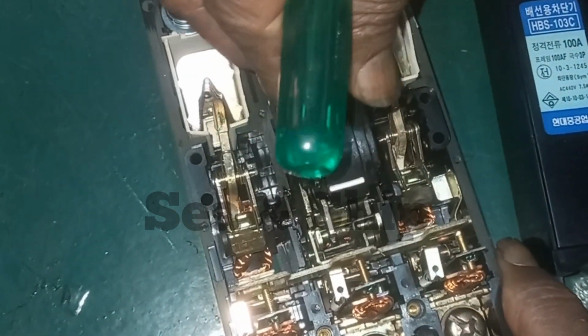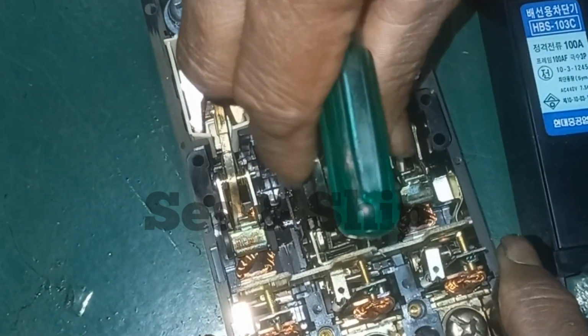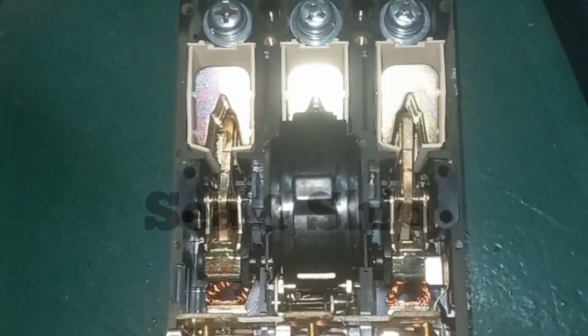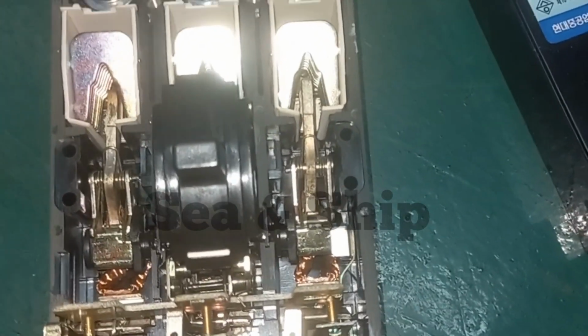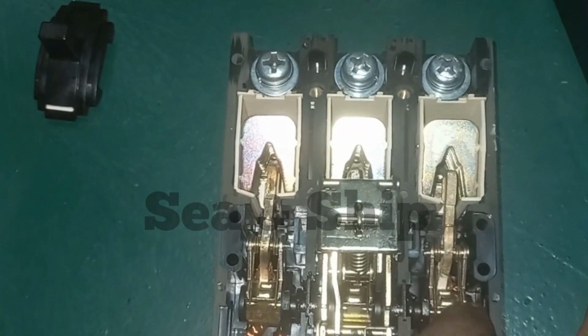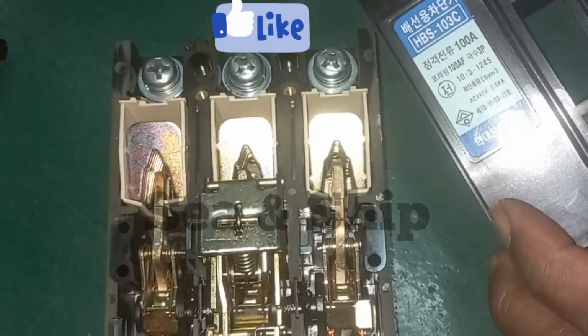Unlike a small MCB in your home, an MCCB is built for high current, from 16 amps all the way up to 2,500 amps. The biggest feature of an MCCB is that its trip settings are adjustable. That means we can set at what current it should trip for overload and for short circuit. This is very important for starting big motors like our main air compressor or ballast pump.